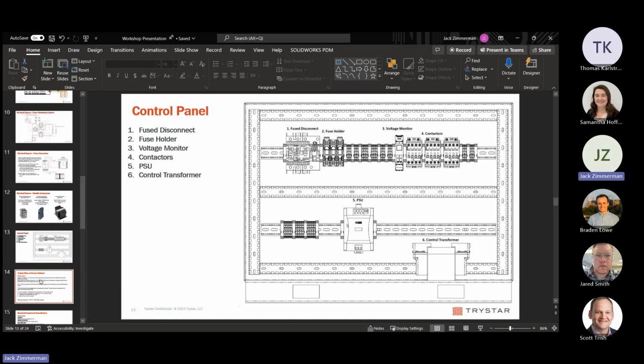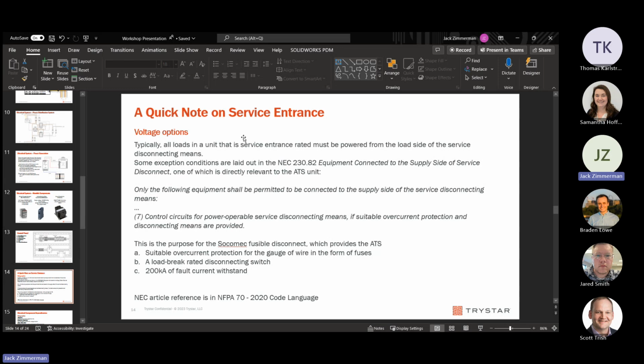I promised to talk about the fusible disconnects quick. So quick note on service entrance. We're pulling taps from the utility in front of the service disconnecting means, which is not allowed per National Electric Code in most circumstances, because there's no overcurrent protection in front of that first breaker. We're pulling straight from the voltage transformer you see up front. There are some exceptions laid out in NEC 230.82, which is equipment connected on the supply side of service. And this is where we managed to pull the exception back in November.